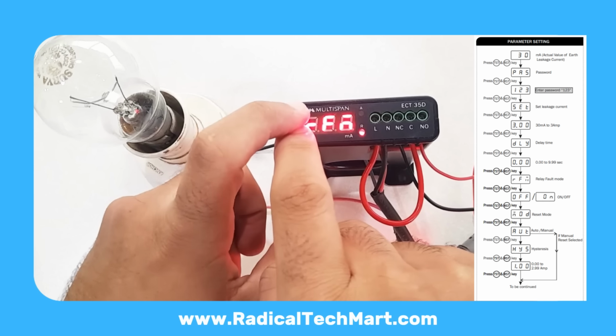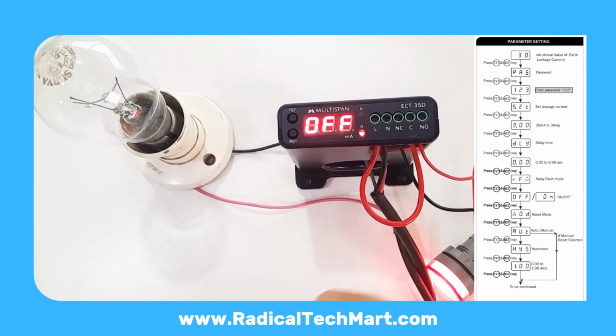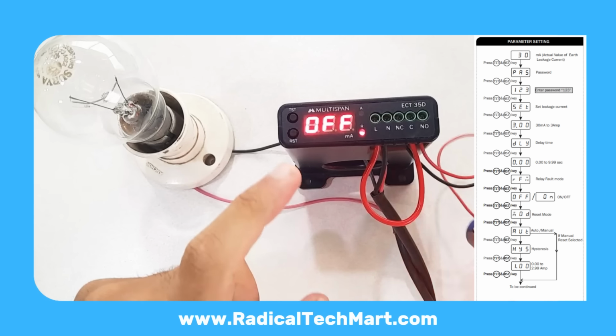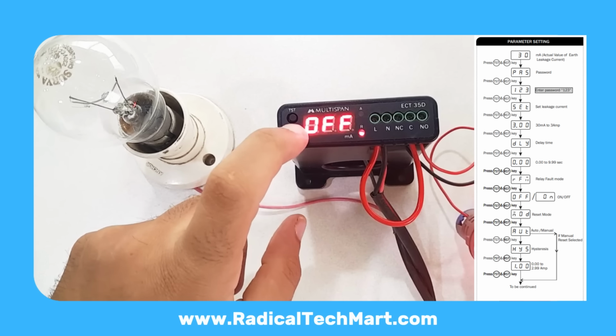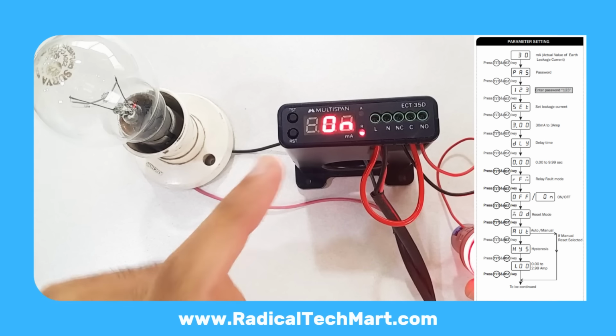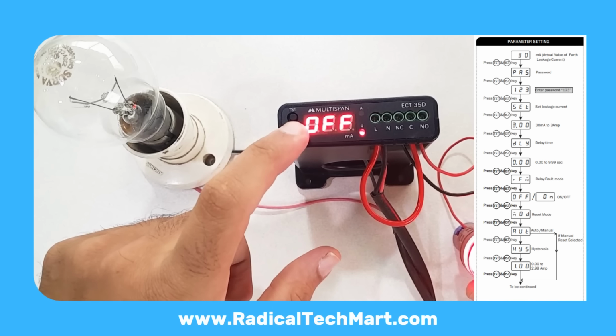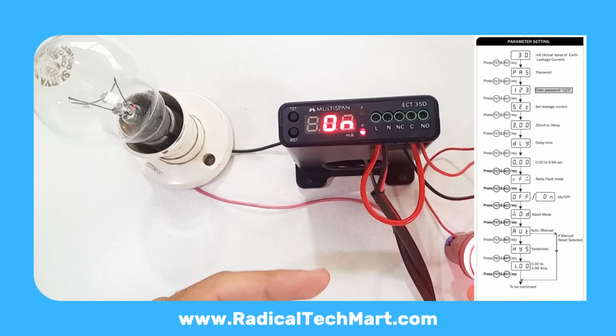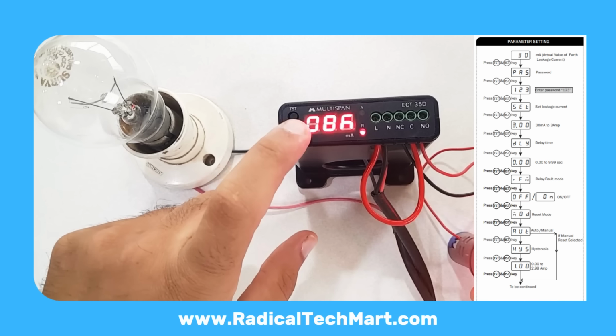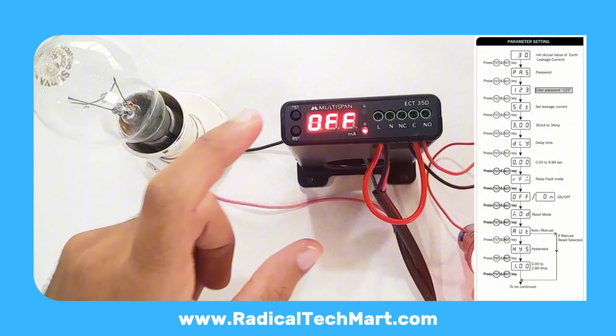Press both buttons again. You'll get relay fault mode. It's currently set to off. This means the relay will de-energize, turn off, when a fault occurs. If you set it to on, the relay will energize during a fault, useful when you want to trip an MCCB shunt or other interlocks.